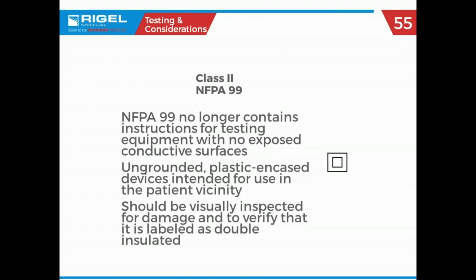So here, and I already gave this one away a little bit earlier: Class 2, the plastic box outside with the chassis inside. NFPA 99 2018 says you don't have to do electrical safety testing on that anymore. So a lot of your infusion pumps, unless they have a ground pin, which some still do, you don't have to do electrical safety. We call them a guide pin. Guide pin? Yeah, they're not called a ground pin, and they don't go to anything.